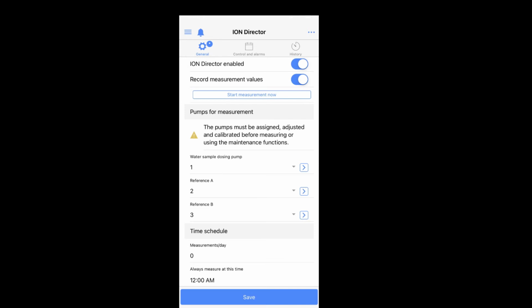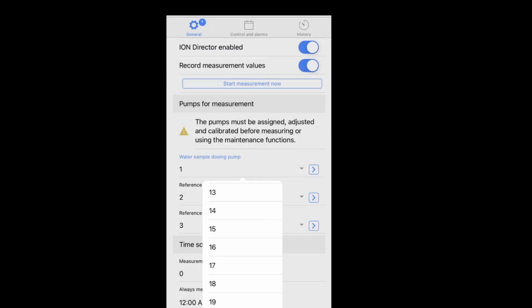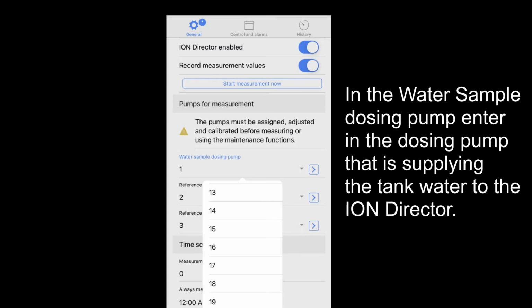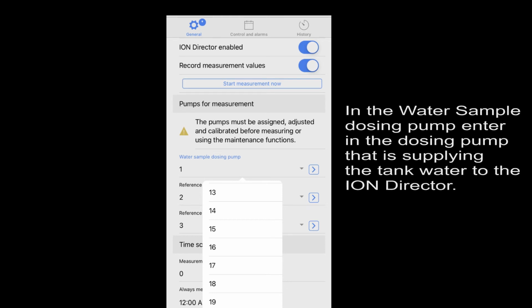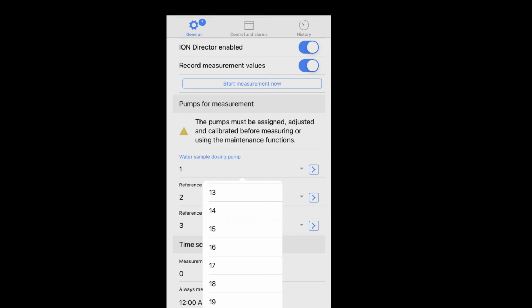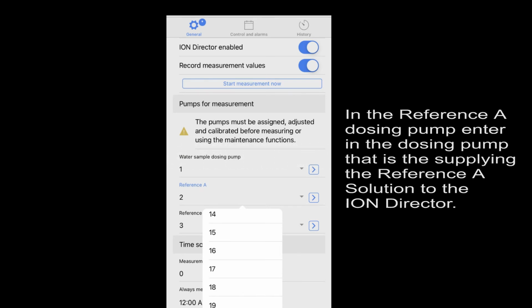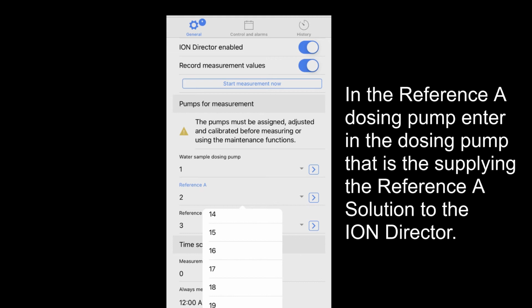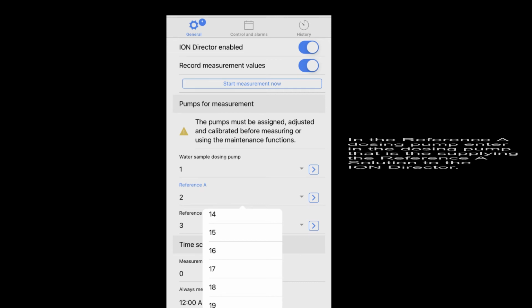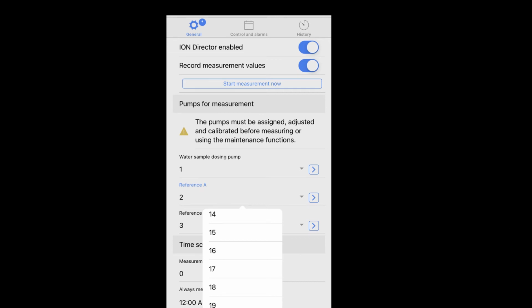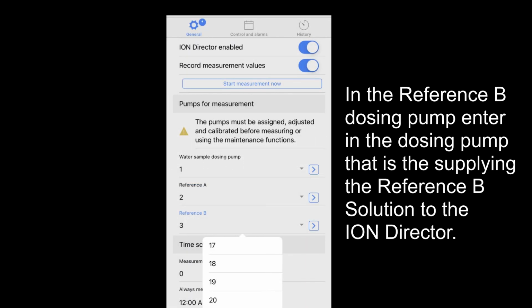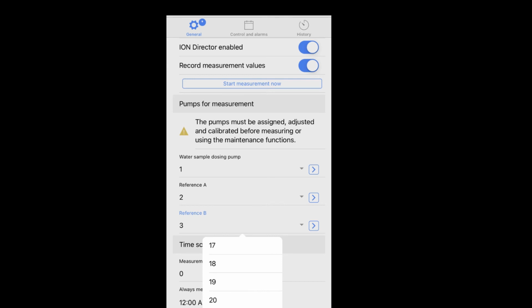Next, we need to configure which pumps will use the ion director. Scroll down to the pumps for measurement. In the water sample dosing pump, enter the pump that will be used to provide your tank water to the ion director. For me, it was pump 17. Next, in the reference A pump measurement, enter the pump that will be providing the reference A solution to the ion director. For me, it was pump 18. Last, in reference B's pump measurement, enter the pump that will be providing the reference B solution to the ion director. For me, it was pump 19.